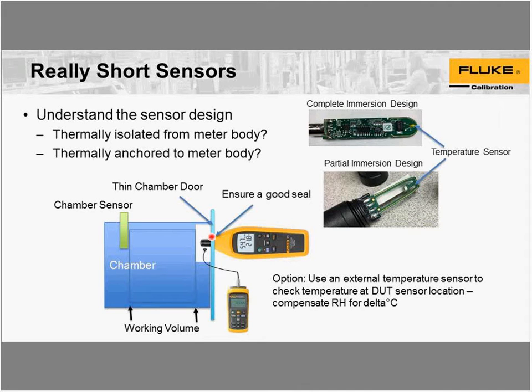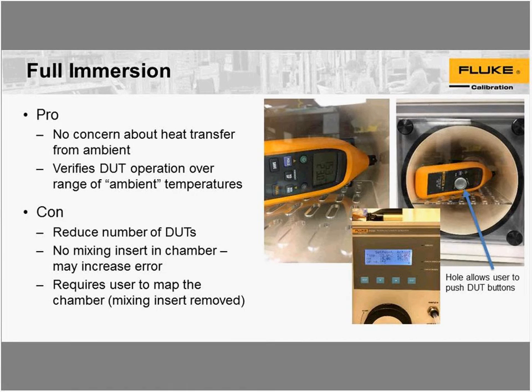Okay. Here's the entire unit in the chamber. The problem here is it may be difficult to reach in there and push buttons or take readings off the display. I drilled a hole in this door so that I could push buttons with a stick if I need to. It worked really well.